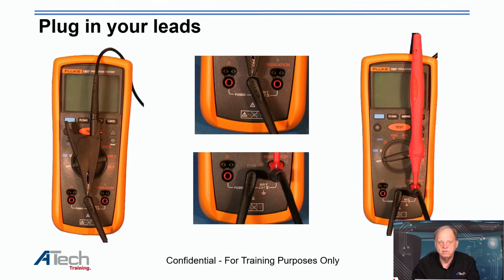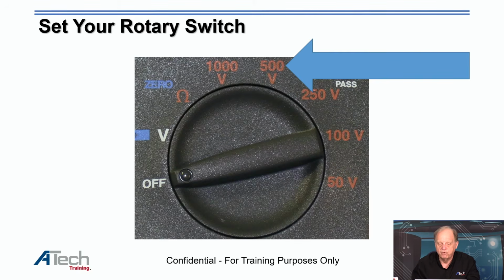The next thing we need to do is set your rotary switch at 500 volts. That's what we're going to use, none of this 2 volts or whatever for a regular meter. We're going to use 500 volts to test it out, and the first thing we're going to do is test the accuracy of the meter itself. So we're going to put 500 volts.